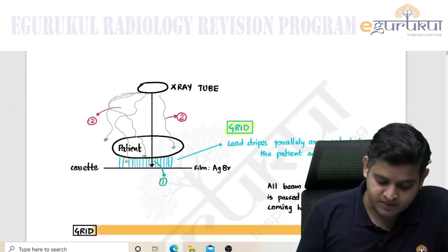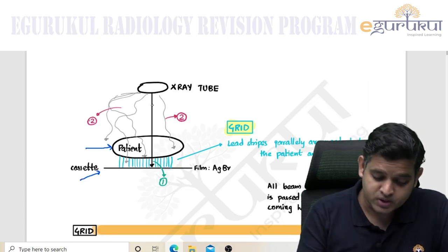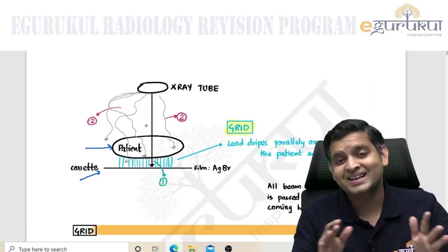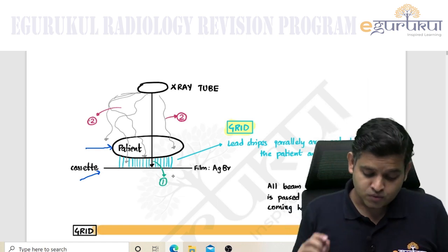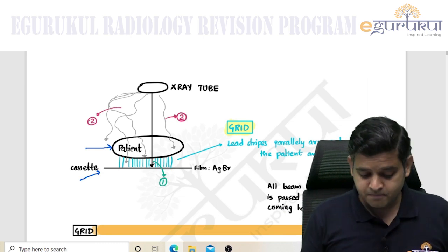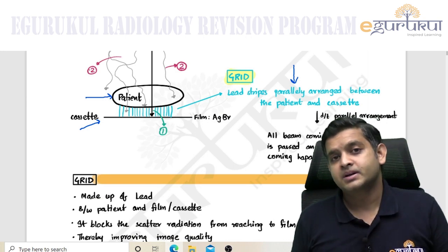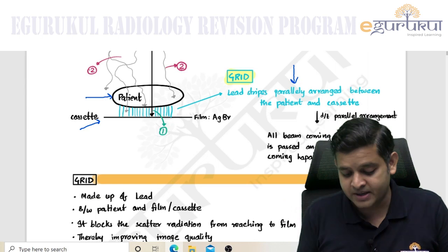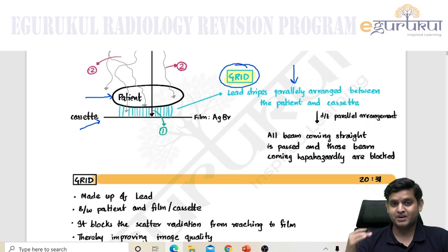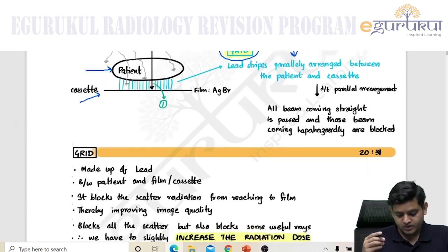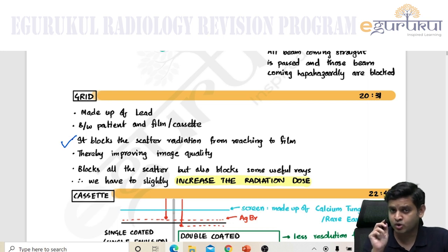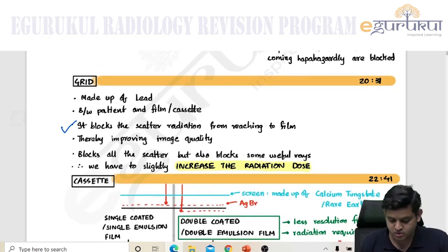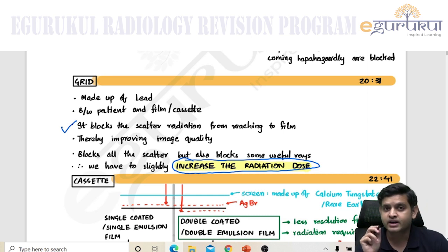After the beam passes through the patient, a lot of scattered radiation reaches the cassette and reduces image quality. To address this, between the patient and the cassette, we place parallelly arranged lead stripes — this is the grid. The grid blocks scatter radiation from reaching the cassette, thereby improving image quality, but at the cost of increasing radiation dose to the patient.